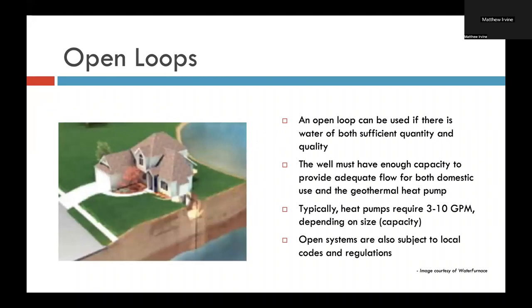An open loop can be used if there is water of both sufficient quantity, that is to say you have enough of it, and quality, that is to say it's not full of gunk and debris and sediment and other things that are going to cause issues in a heat exchanger. The other thing to bear in mind is that the well must have enough capacity to provide adequate flow for both domestic use, that is washing hands, toilets, showers, washing dishes, and the geothermal heat pump, because the heat pump will come on anytime the house needs heating or cooling. It's not going to have any idea whether or not you're having a shower or doing dishes. And typically a heat pump is going to require, residentially, somewhere between 3 and 10 gallons per minute when it's running, again depending on the size or capacity of the heat pump. And then open systems are also very often subject to local codes and regulations. Next.